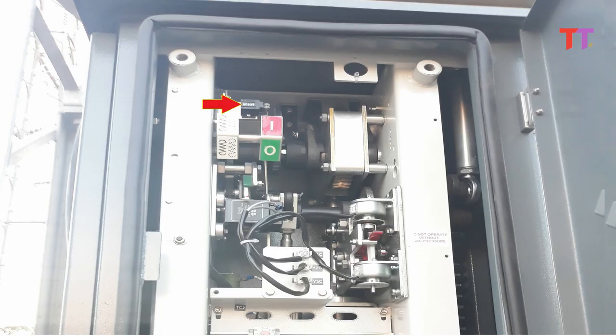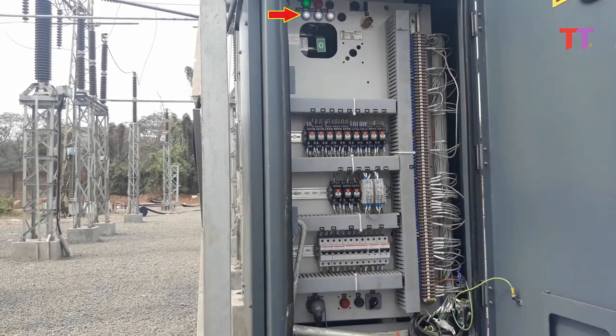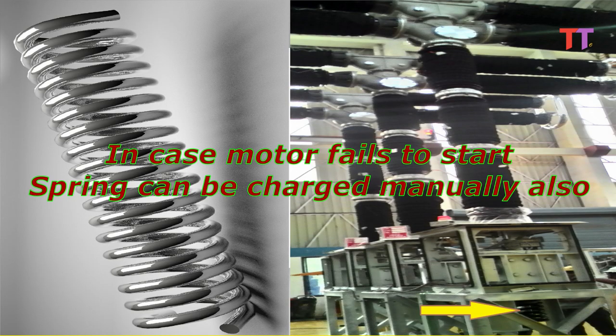This counter shows number of operations of circuit breaker. This is closing coil. Here we can see tripping spring. These are different indication lamps, such as spring charging, close, open, etc. This is selector switch for selection of local or remote mode of operation. These are MCBs, this is TB housing connections, and these are contactors. In case motors fails to start, spring can be charged manually also.